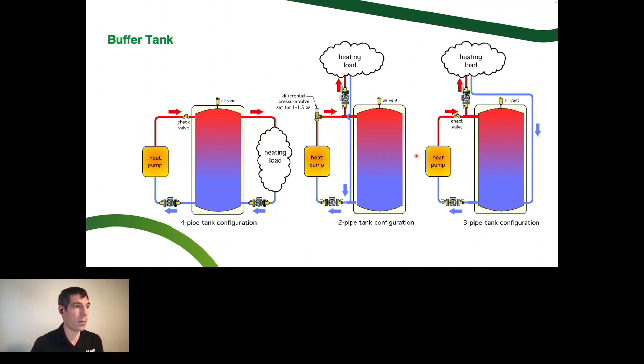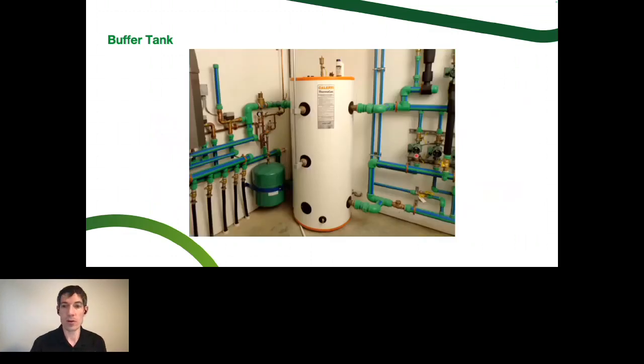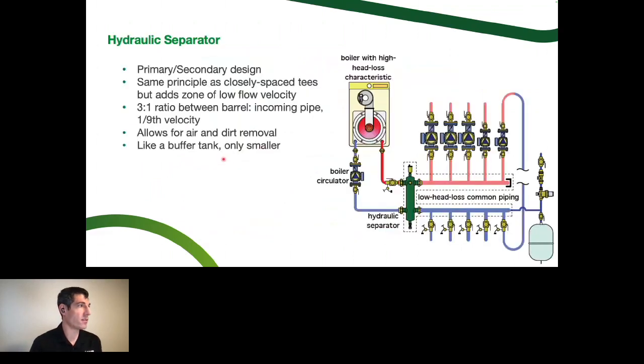This is what a buffer tank looked like in the solar thermal days, when we were in that industry more, before PV just kind of did a better job and got less expensive quicker. So this is just a 4-port buffer tank for a geo exchange solar combo system. Okay, the third choice is a hydro separator. Low loss header and hydro separator are synonyms for this device. So this is primary, secondary in a box essentially.